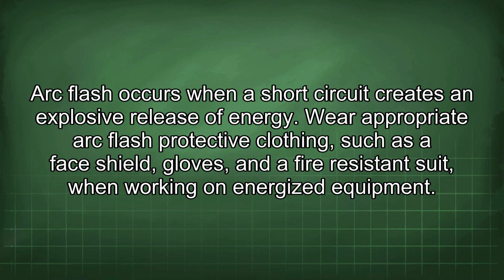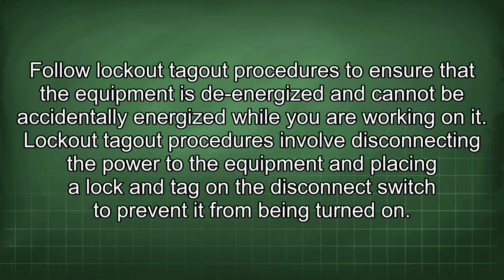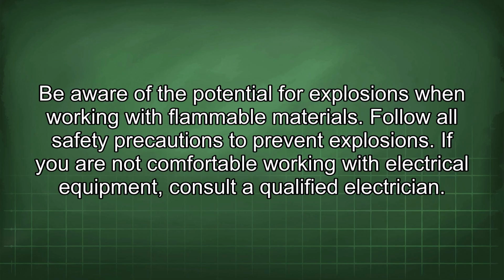Wear appropriate arc flash protective clothing, such as a face shield, gloves, and a fire-resistant suit when working on energized equipment. Follow lockout tag-out procedures to ensure that the equipment is de-energized and cannot be accidentally energized while you are working on it. Lockout tag-out procedures involve disconnecting the power to the equipment and placing a lock and tag on the disconnect switch to prevent it from being turned on. Be aware of the potential for explosions when working with flammable materials. Follow all safety precautions to prevent explosions. If you are not comfortable working with electrical equipment, consult a qualified electrician.